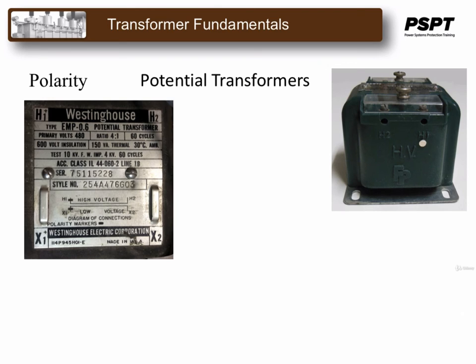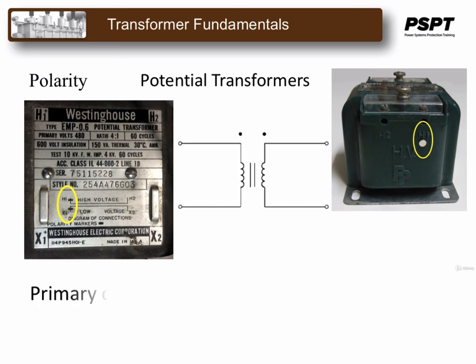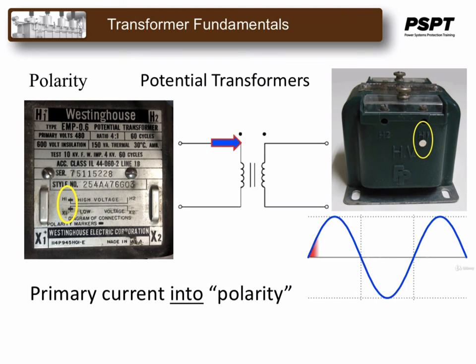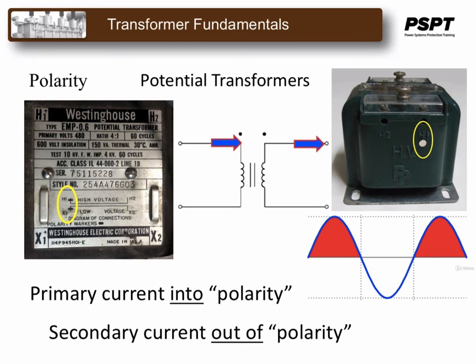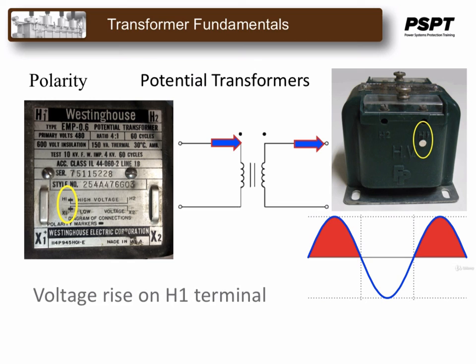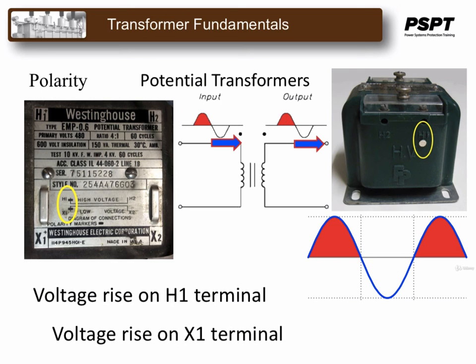Designating the polarity of a PT is very important and done much the same as in the case of a CT, by marking the PT primary and secondary terminals and/or indicating it on the nameplate. Again, this is especially important when PTs are used for relays and revenue meters. As in the case of the CT polarity, the primary and secondary terminals are marked in such a way that when the primary current is positive during the sinusoidal half cycle, that's current into a polarity spot, the secondary current will be out of the polarity spot on the secondary. Or in terms of voltage, since we're dealing with voltage transformers, a voltage rise on the H1 terminal gives a voltage rise on the X1 terminal.